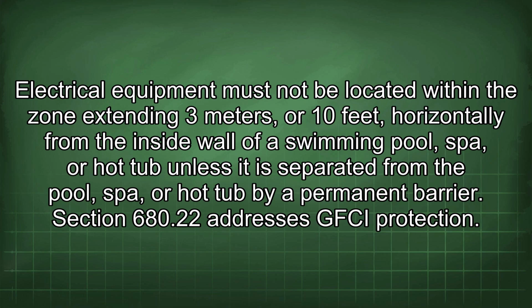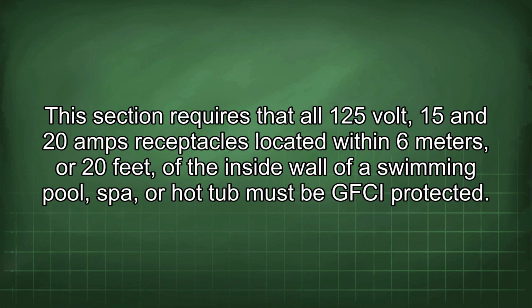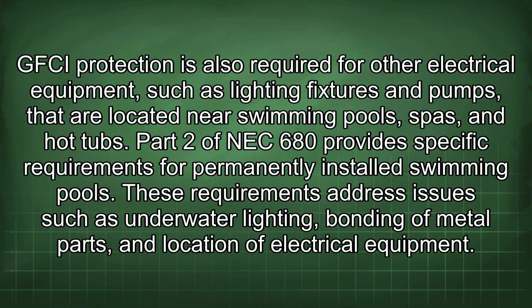Section 680.22 addresses GFCI protection. This section requires that all 125 volt, 15 and 20 amp receptacles located within 6 meters or 20 feet of the inside wall of a swimming pool, spa, or hot tub must be GFCI protected. GFCI protection is also required for other electrical equipment, such as lighting fixtures and pumps, that are located near swimming pools, spas, and hot tubs.